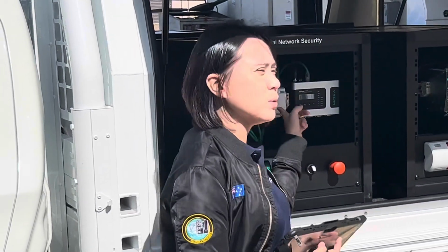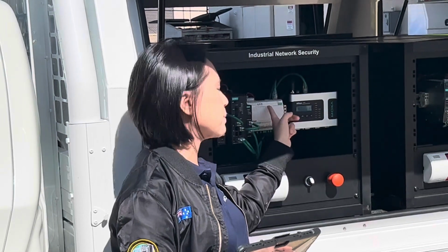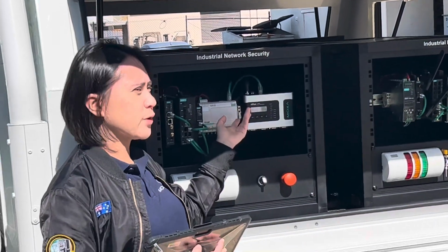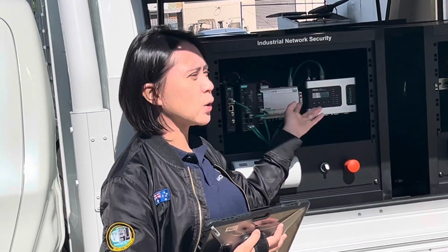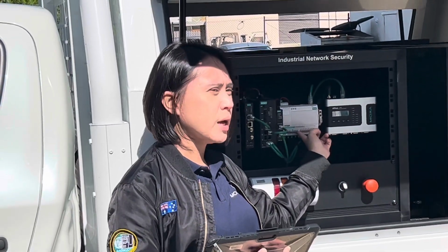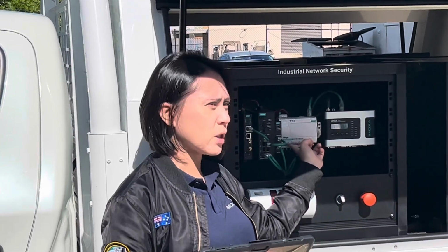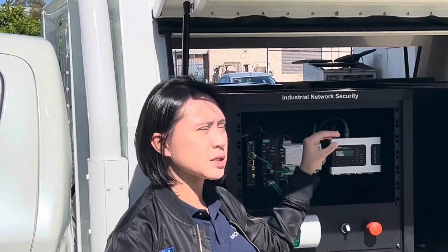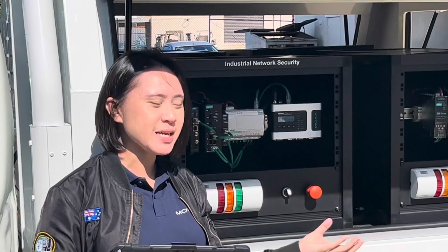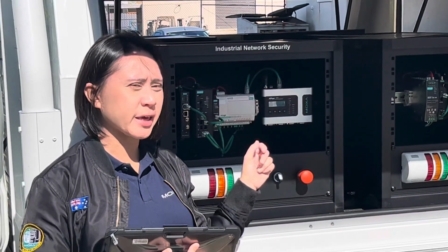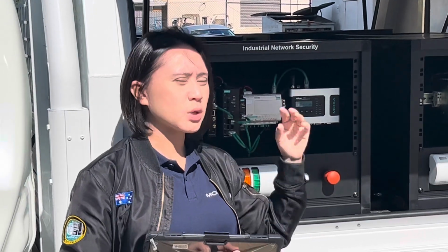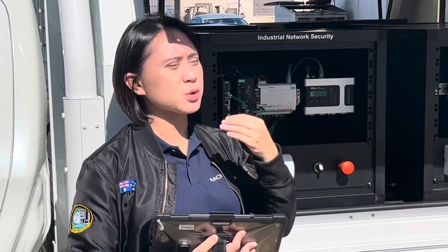And this is the I/O. Here we use it to monitor, as an example, your field device, maybe a meter that can talk Modbus. This is the I/O that has several different I/O types, so you can have different combinations, ranging from digital input, output, analog input, output, different models, and you have some intelligence inside, I would say. It's not as smart as your PLC, but it has a function called Click&Go. With Click&Go, you can set some if-else logic. So if this DI is on, the DO will be switched on as well.